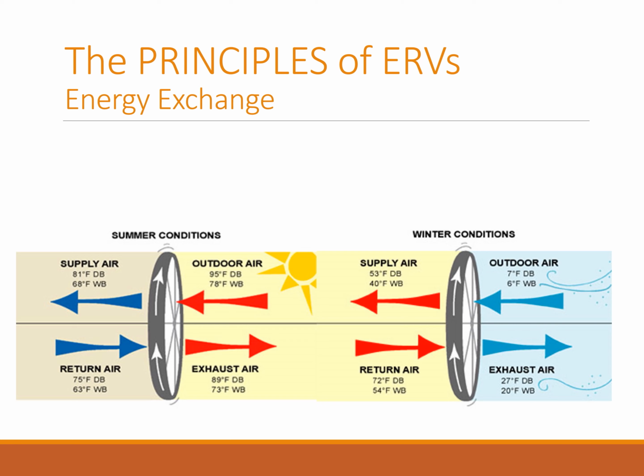In winter conditions, the outside air enters the system at 7 degrees dry bulb and 6 degrees wet bulb. The return air is 72 degrees dry bulb and 54 degrees wet bulb. As the outdoor air passes through the energy recovery medium, the temperature is raised by mixing it with the return air from the space. The result is a 53-degree supply air to the HVAC system or space, rather than a 7-degree supply air, which would be the case without an energy recovery solution in the system.